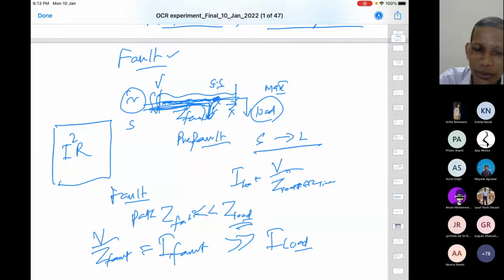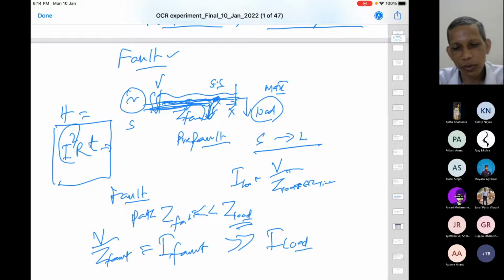Any component, any element associated with the current, this current will flow. If you have a transformer here, this current will also flow through that transformer. And the series resistance or equivalent impedance of the transformer conductor will also get heated. Any conductor will be heated in terms of its associated resistance. And because this is a square term and the fault current is substantially higher than the normal current, a lot of heating will be there. But the heat, H, equals I square R into T, time. Agree? So with more time, the amount of heat at each element will also be more, and that may be detrimental to the system. So if the fault continues, the chance of damage to each element is more. Agree? And if you can remove the fault quickly, then there is no chance of damage.